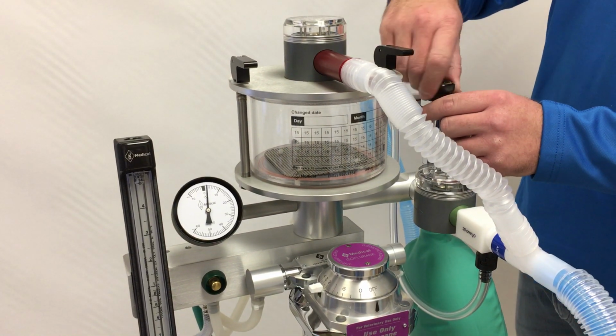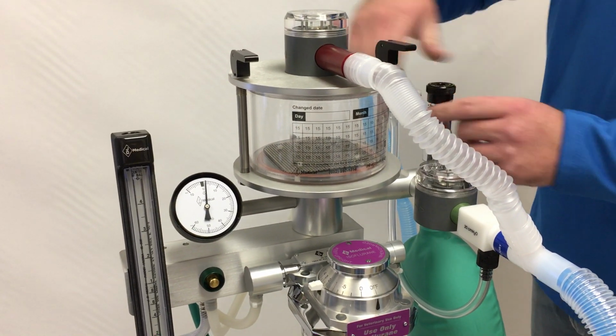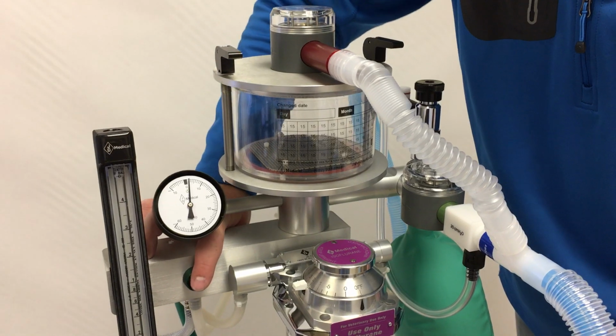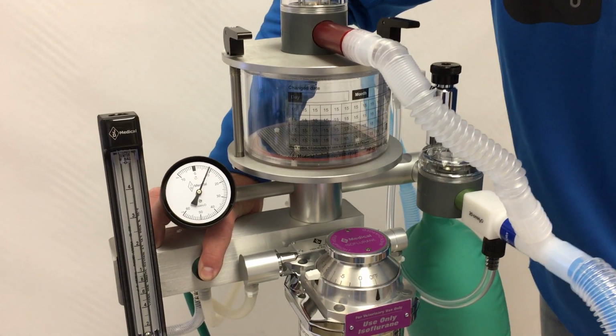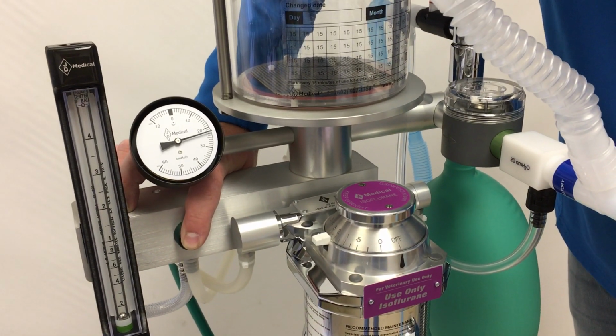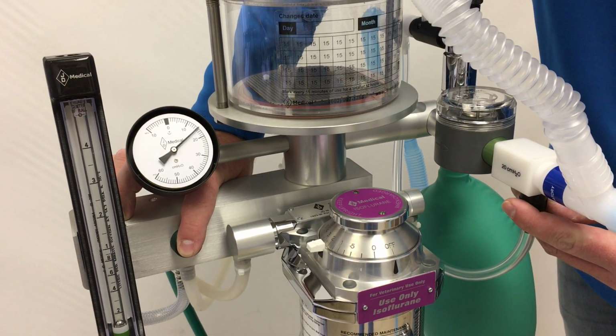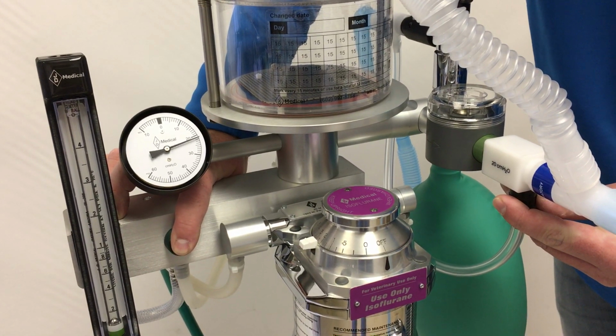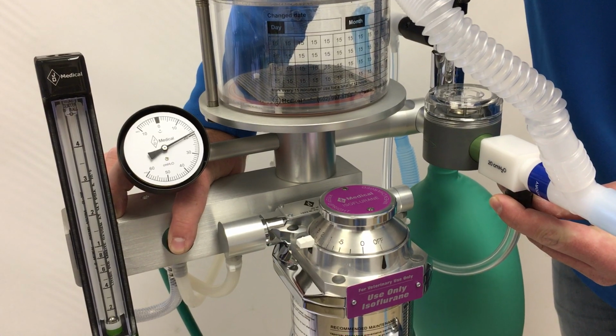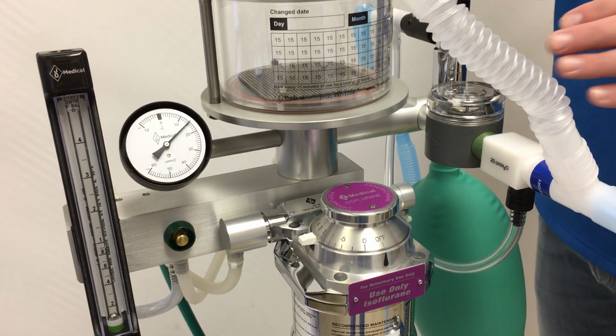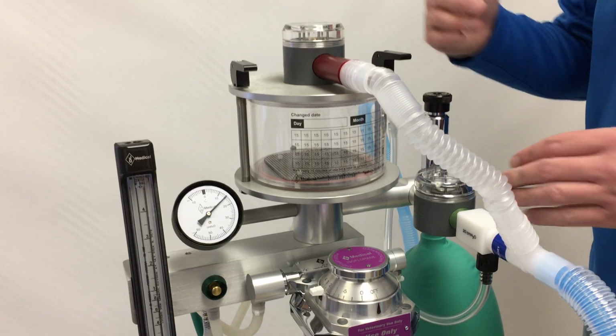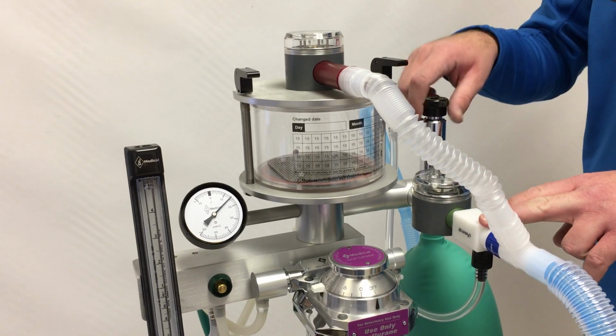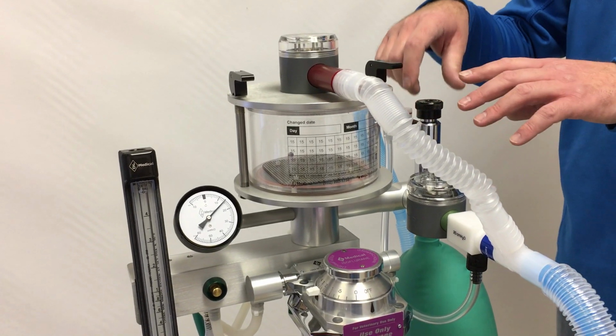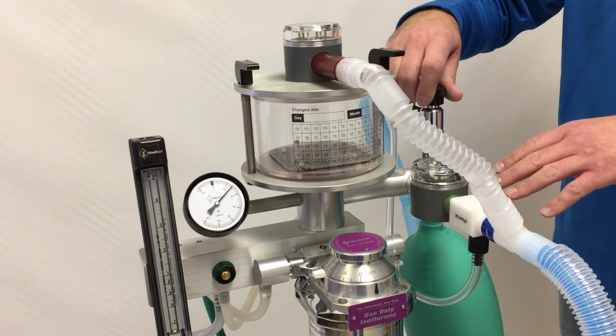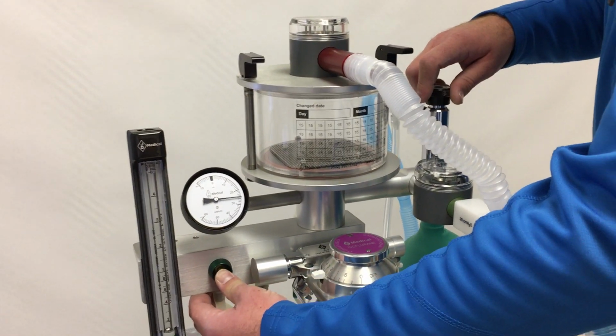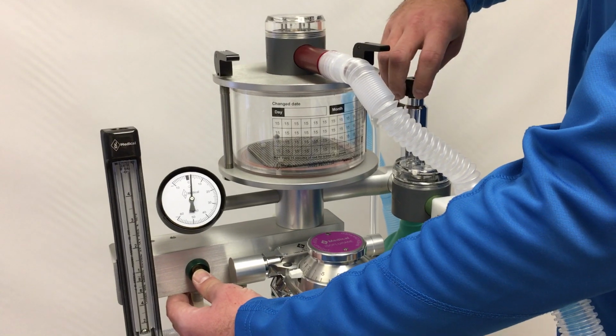If we close the pop-off valve, now is where we will see the valve function. So we'll build up some pressure using the flush, and you can hear the valve opening. So we bring it up above 20, and it will vent and return the machine to a safe pressure, making a noise so that you're alerted to a possible equipment malfunction or an accidental closure of the pop-off valve, giving you time to open the valve and relieve that pressure.